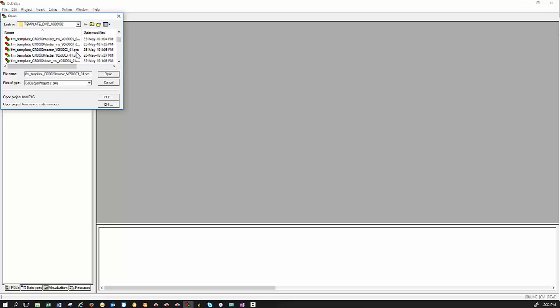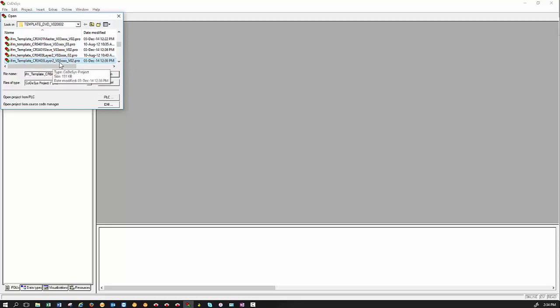Next step is now if you double-click on your Codesys icon it should come up with this window. Then the first step would be, say File and say New from Template. You will find this template folder is installed by Codesys itself. So then if you scroll down and look for your controller, in my case I am programming a CR0403. So I use CR0403 Layer 2 Version 3 and that indicates the firmware version that I'm running on the controller. So select that and click Open.